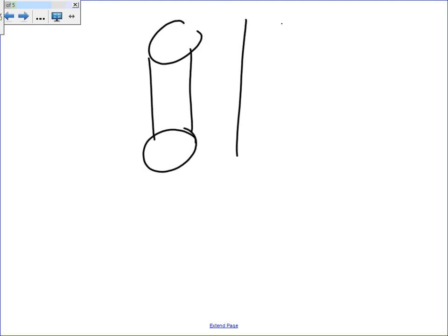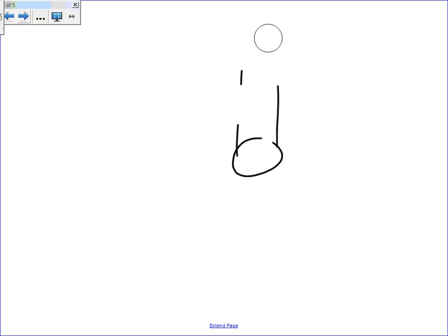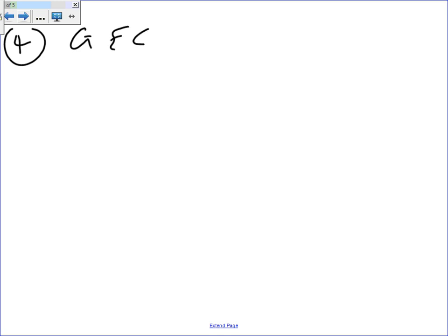I like to draw these just because. So here's my conduit at the end. Well, let's do the conduits at the end after we do the equipment grounding conductor and so forth. Actually, it's easier. Let's do number 1, 2, 3, 4. We did 4. 4 is the grounding electrode conductor. You're going to go to table 250.66. That's a piece of cake.